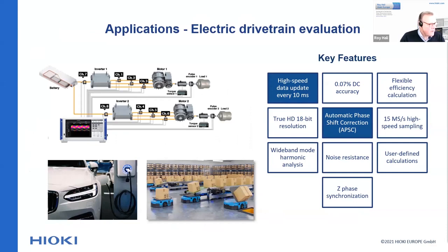Here we see a dual drivetrain application as well, where we use DC inputs and we can measure up to 3 channels, or the input phases of the motor, and at the same time the mechanical power at the axis of the motor. This is becoming more and more important because of the development of automated vehicles for distribution centers and similar uses, but also of course for electrical vehicles where performance is required. In this case, the automatic phase shift correction function is important, and also the high-speed sampling, the high update rate of the instrument.